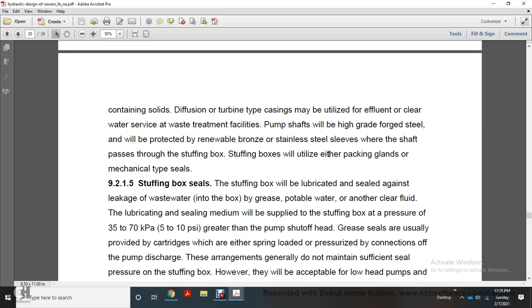Stuffing boxes will utilize packing glands or mechanical type seals. These stuffing box seals prevent leakage of wastewater into the box, using grease, potable water, or other clear fluid. The lubricating sealing medium will be supplied to the stuffing box at a pressure of 5 to 10 psi greater than the pump shut-off head. Grease seals are usually provided with cartridges with either spring-loaded or pressurized connections to the pump discharge.